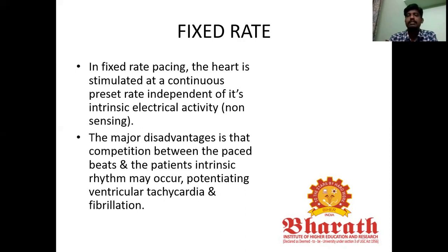First one is fixed rate. In fixed rate pacing, the heart is stimulated at a continuous preset rate independent of its intrinsic electrical activity, in a non-sensing method. The major disadvantage is that competition between the paced beat and the intrinsic rhythm may occur. Potentially, it may result in ventricular tachycardia and fibrillation.